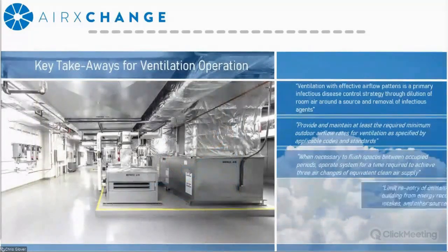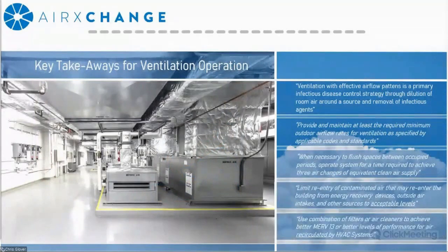All right, so the big takeaway when reviewing these documents, and there's a couple hundred pages worth of documents here, is the importance of ventilation as a means of mitigation. Ventilation with effective airflow patterns is a primary infectious disease control strategy through proper dilution, which basically states you're going to want to keep your ventilation system operating and optimize it to the best of your ability to provide proper dilution. You're going to want to provide at least the required minimum outdoor ventilation rates as specified in Standard 62. Now, for some folks listening in, that may be difficult.